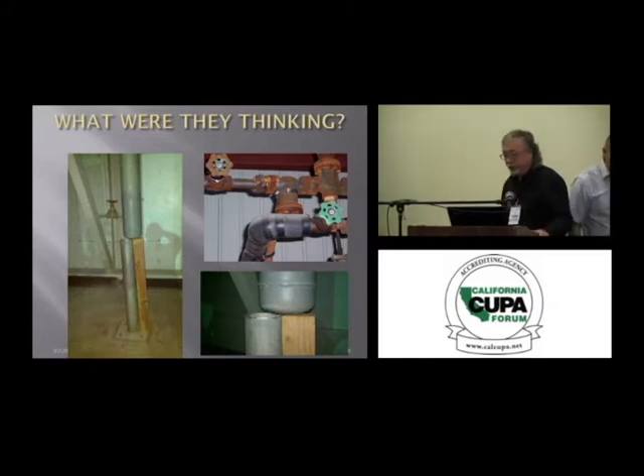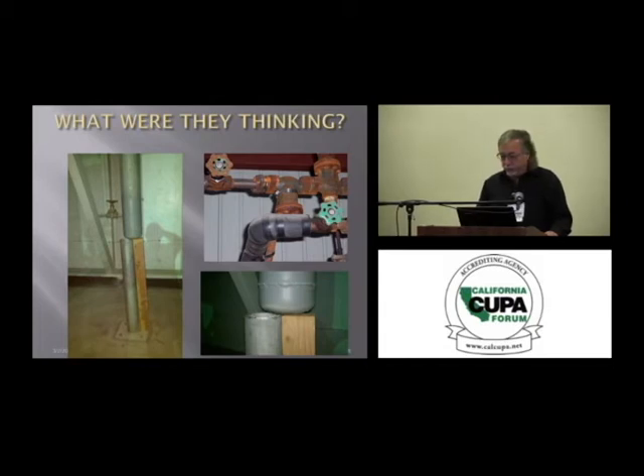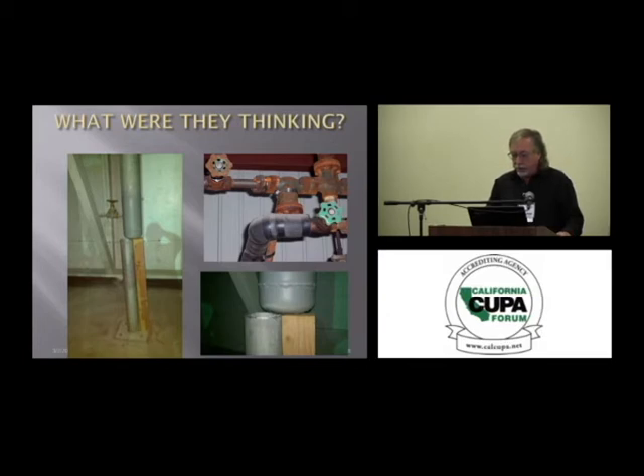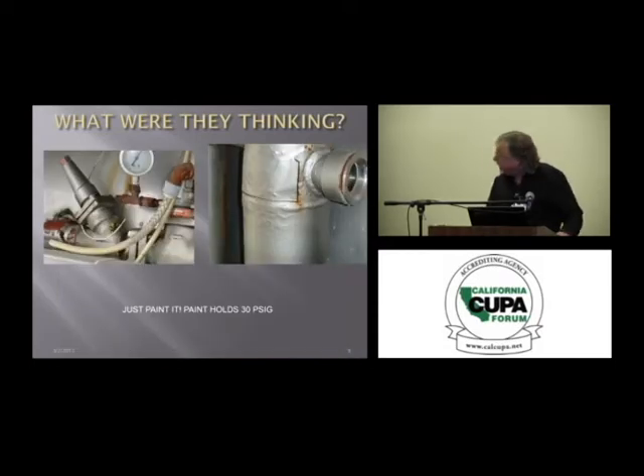The picture on the top right, that's the other end of that pipe that was on top of that flange. And that was actually on a suction line. This is the liquid line it's supporting. It fell off a couple times, so they put a couple hose clamps around it to support it a little bit more so it wouldn't fall down. Top left-hand side, how does that valve look on that gauge? Would you want to operate that valve?